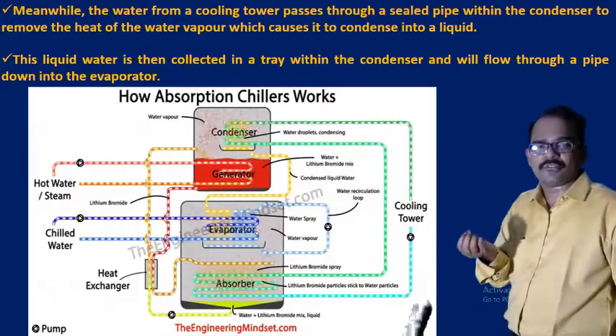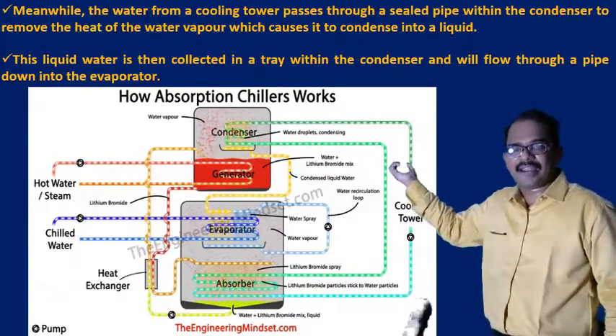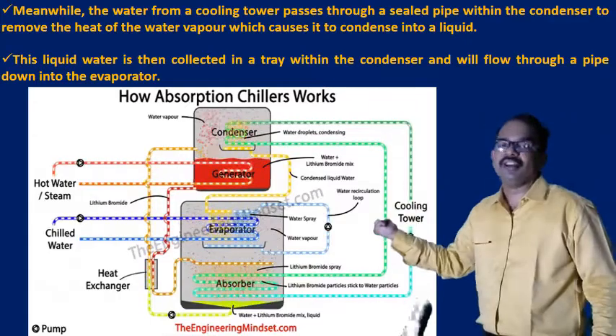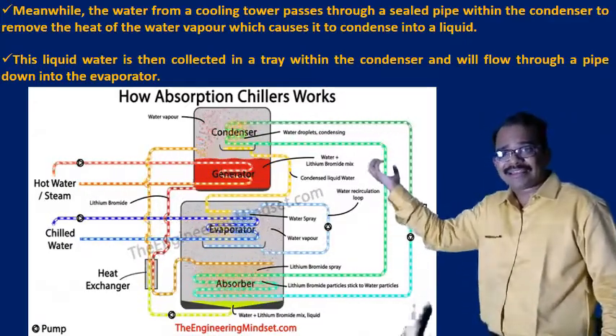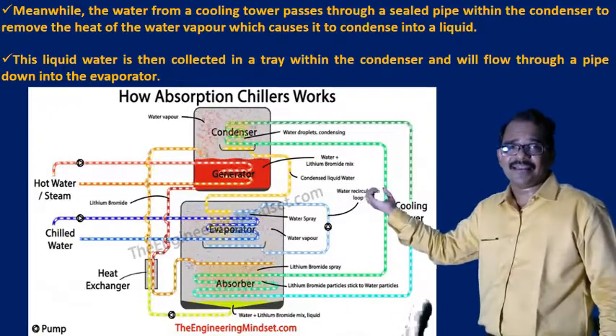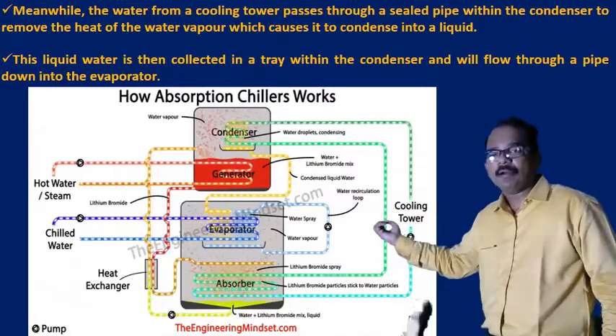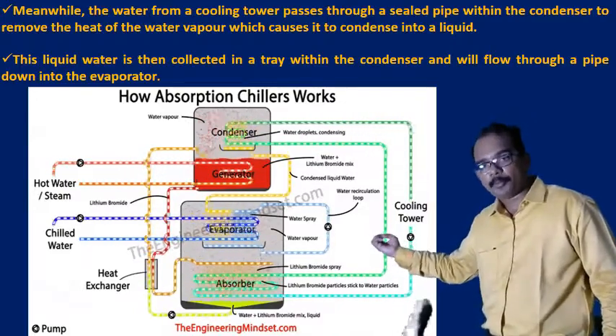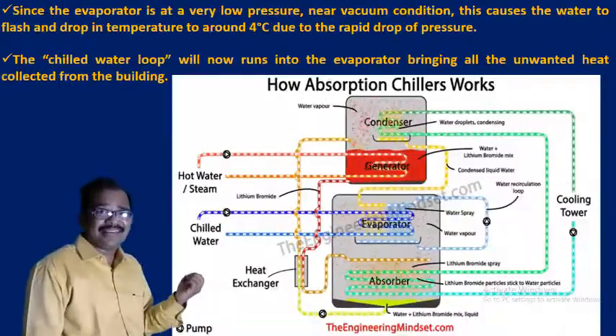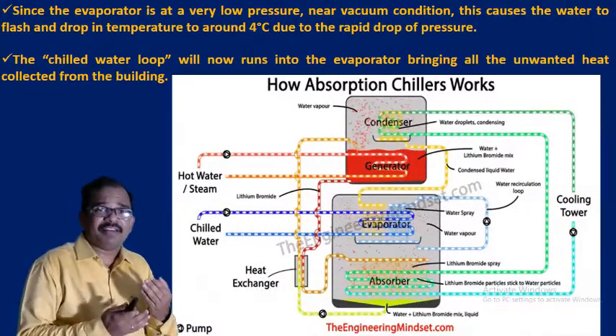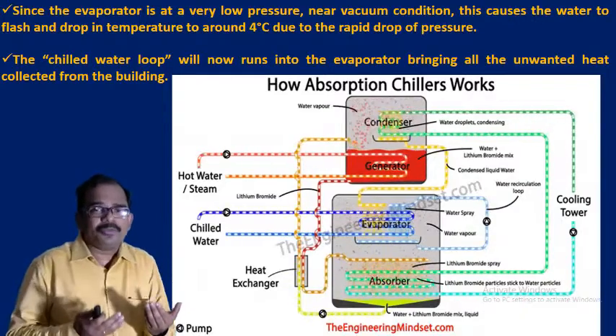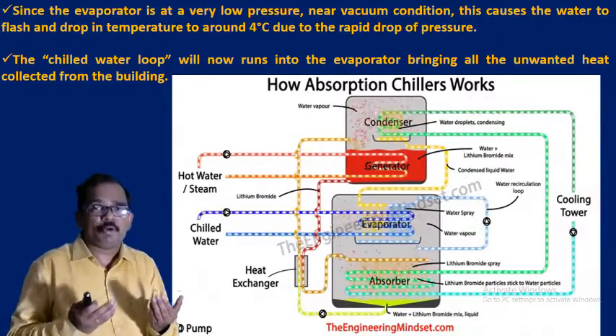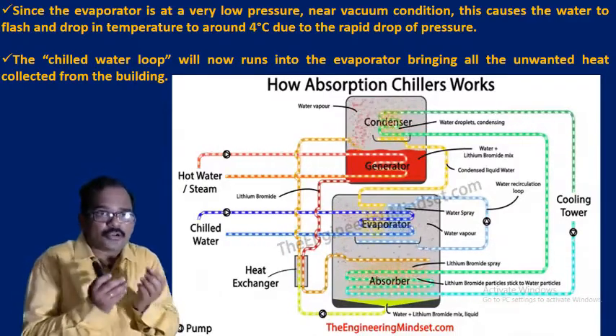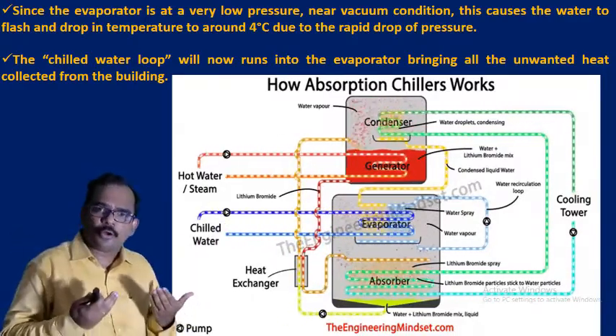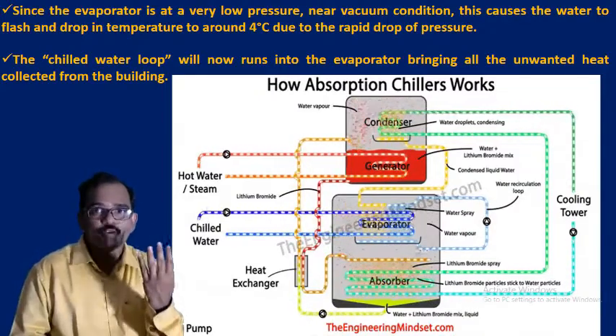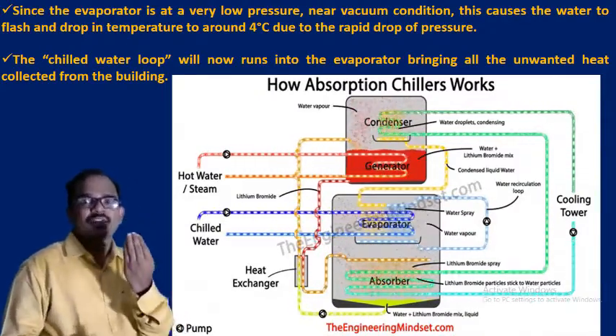Now what happens, the cooling water of the cooling tower will cool this water vapor, and that water vapor will now condense into liquid, and that liquid water will again be collected in a tray within the condenser and will flow through a pipe down to the evaporator, which is there in the bottom component or the bottom chamber. Since the evaporator is operated at a very low pressure, that is near vacuum condition, that is 0.0084 atmospheres, this causes the water to flash and drop its temperature to around 4 degrees centigrade due to rapid drop of pressure, as we have seen in concept number 1.